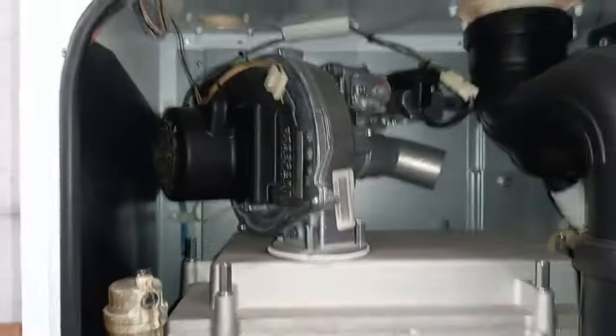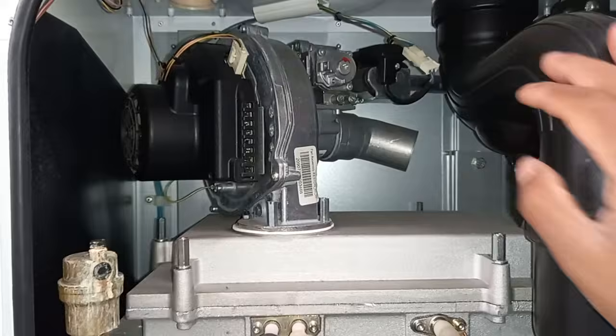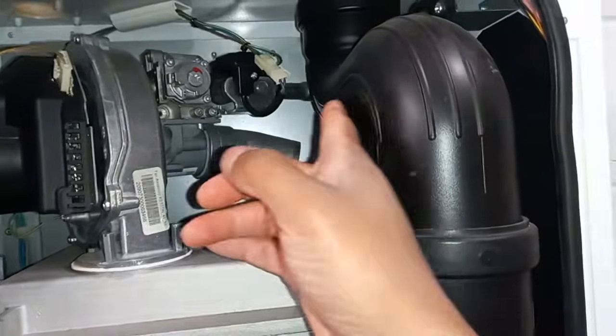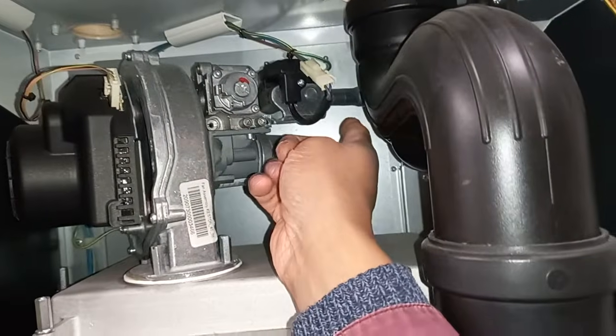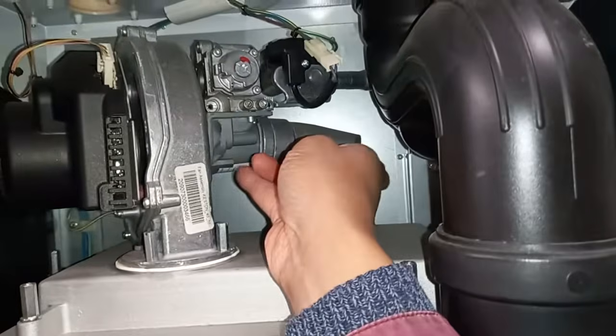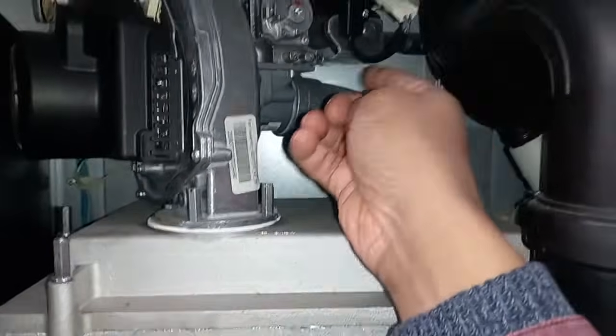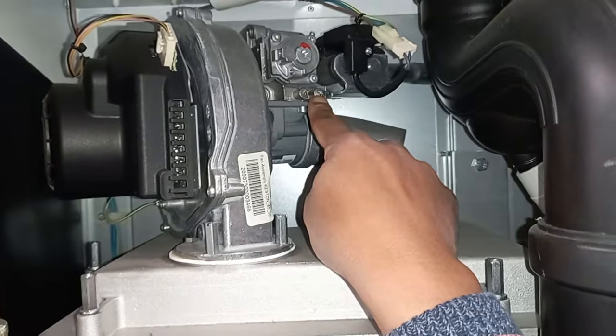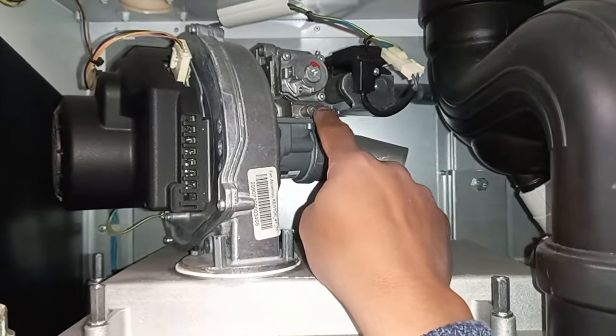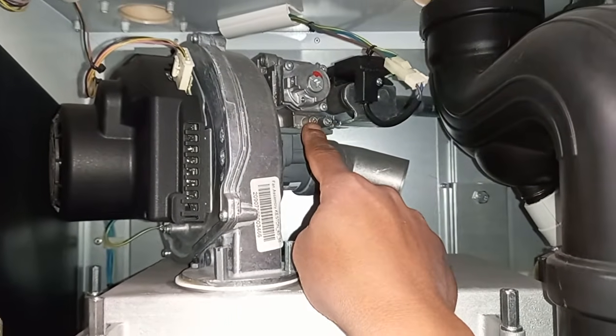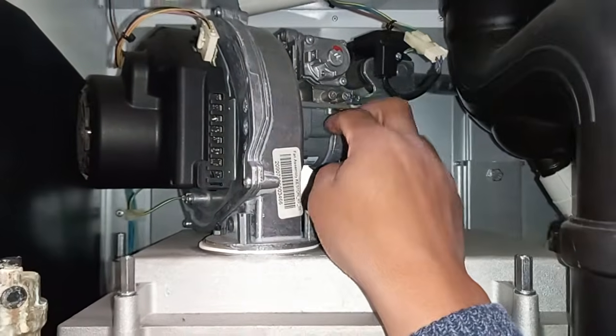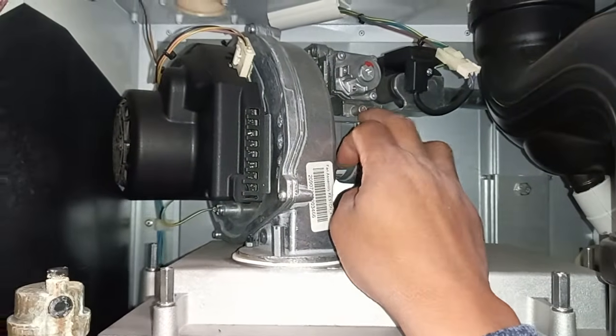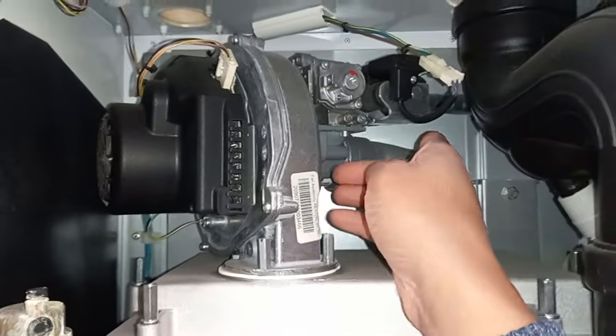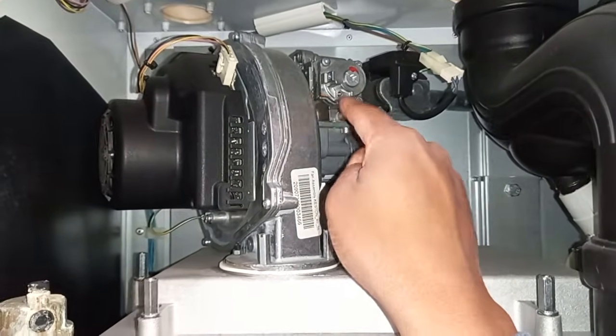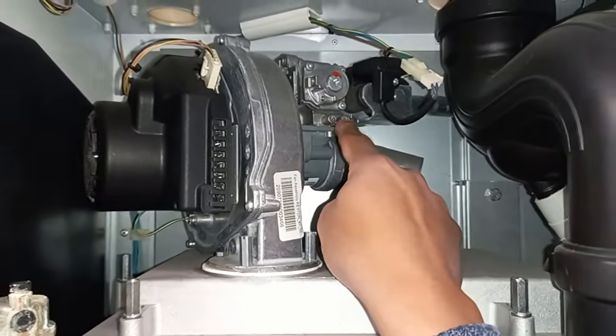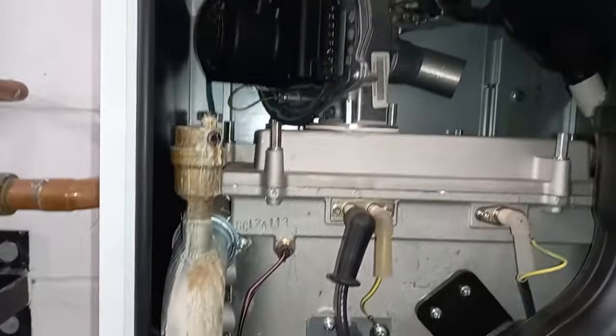All right, so always remember with the working pressure, normally the working pressure is going to be on the incoming of the gas supply. So I see the gas supply coming in here on the boiler, it comes up to here, so this is where it's going to be my working pressure. Normally on this particular zero governor, I cannot check the burner pressure, but on other boilers, not this particular type of gas valve, you'd be able to check a burner pressure, and that's normally after the first point, nearer the other side of the gas valve, or after the working point. Hopefully you get my drift.